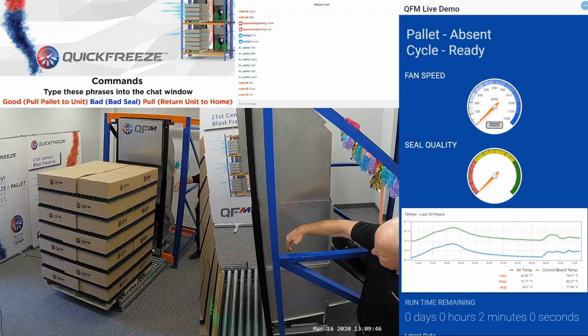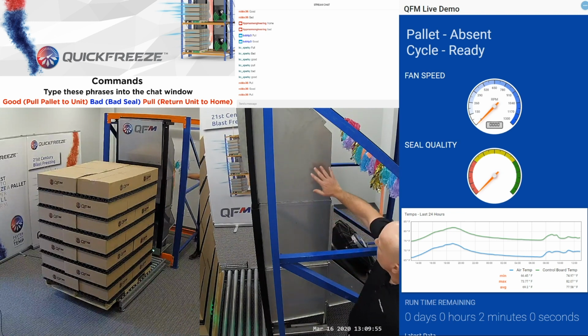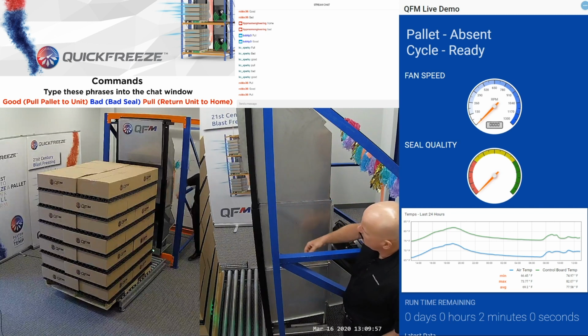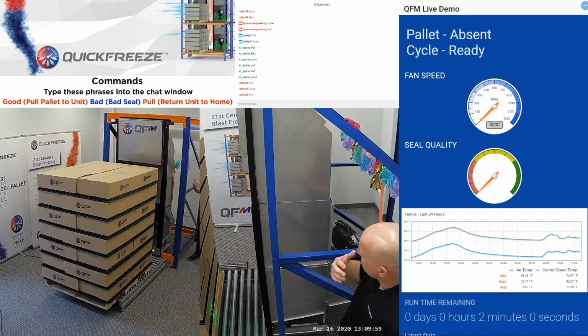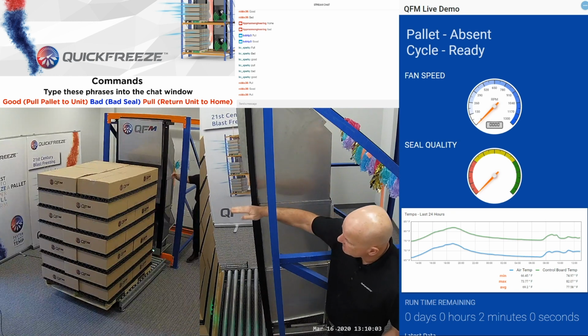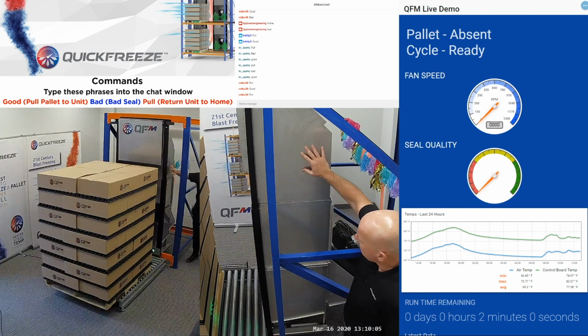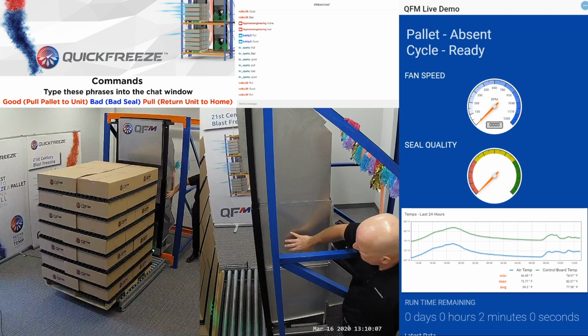So when the pallet approaches the unit, the controls sense that it's occupied, the fan will start, and that reduces the pressure in the plenum. And when the pallet is pressed up against there, the only pathway for the air into the plenum is through the spacer area of the pallet. So we get great velocity through the pallet area.